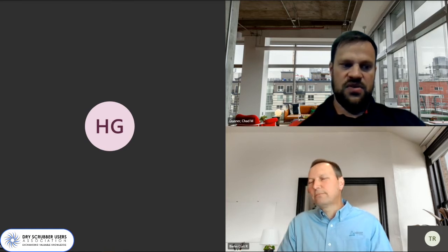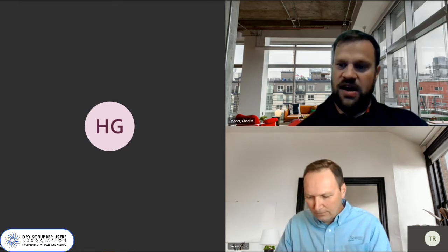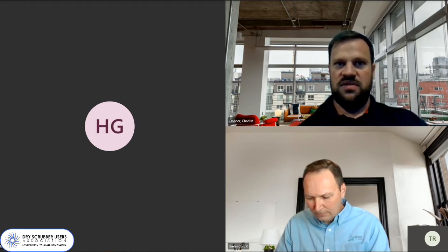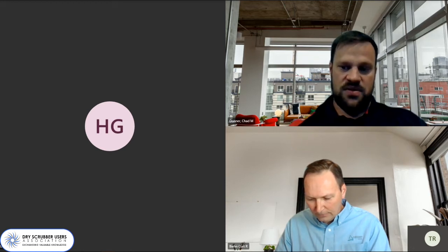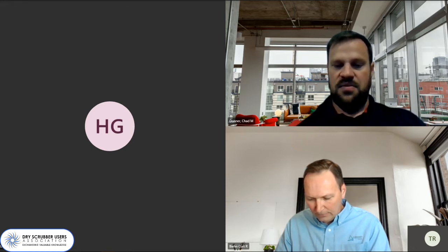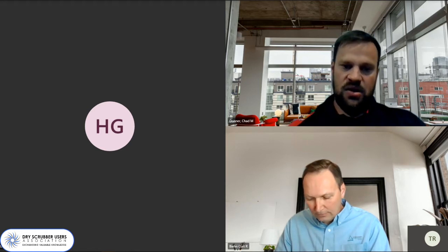Your SCR minimum operating temperature is dependent on SO3. As solar and wind and other renewables become more critical, it's more critical to get the coal units to turn down more. At the same time, our NOx limits are more stringent and becoming more stringent, so we have to keep the SCRs in service. In order to achieve both of those goals, we have to get the SO3 out before the SCR. And again, that's primarily a low load concern.